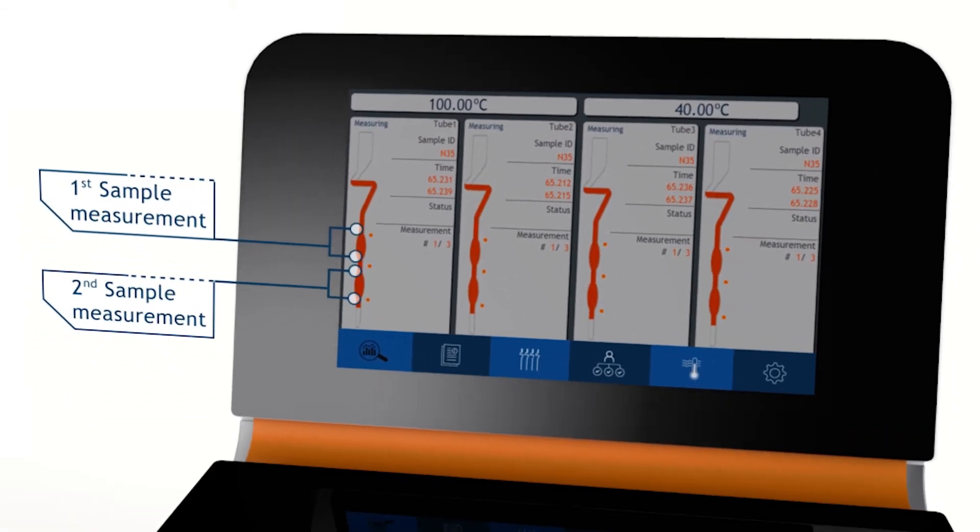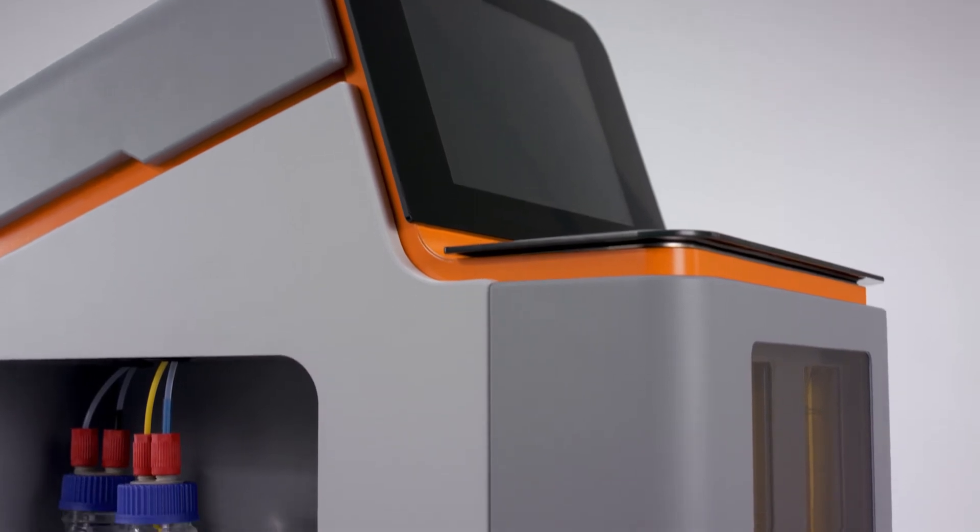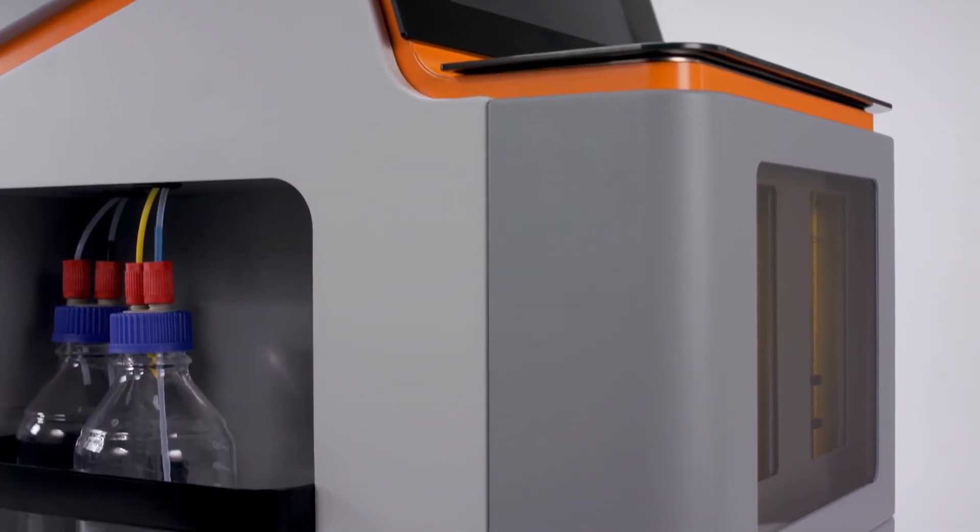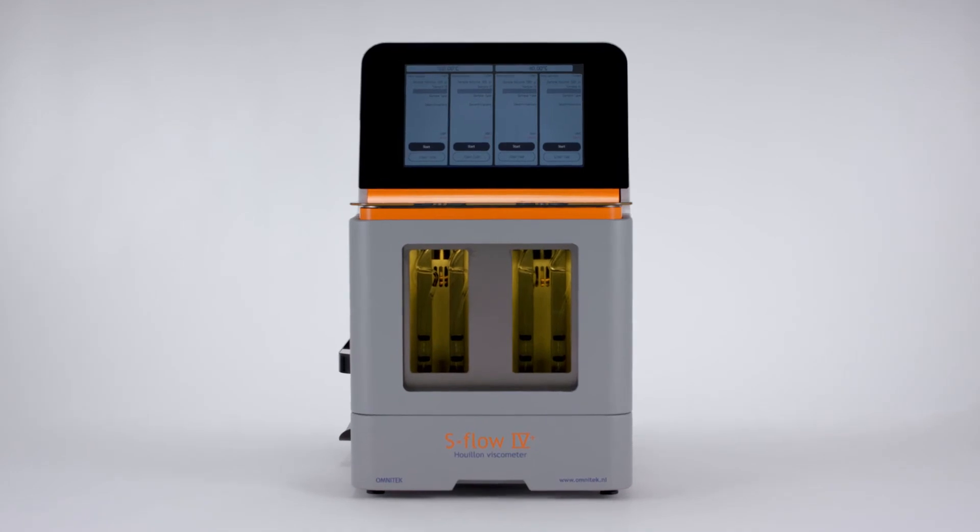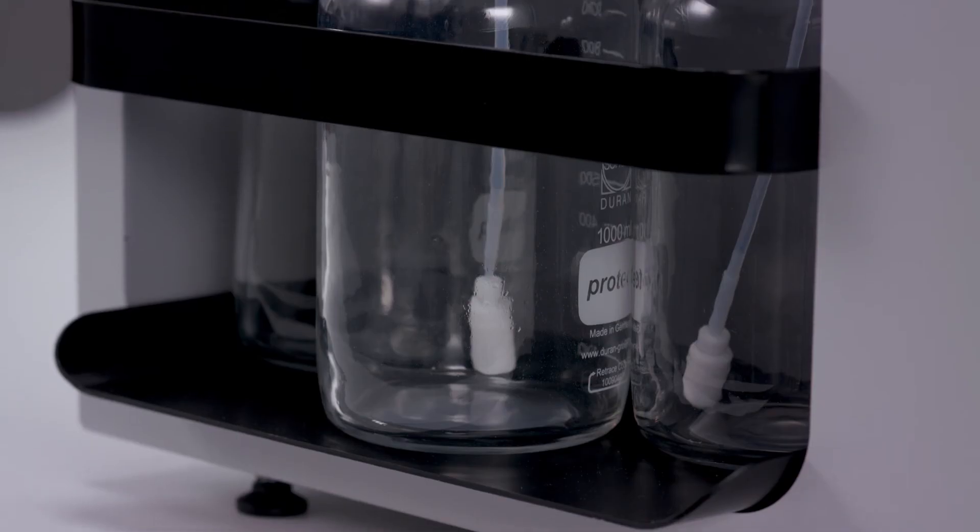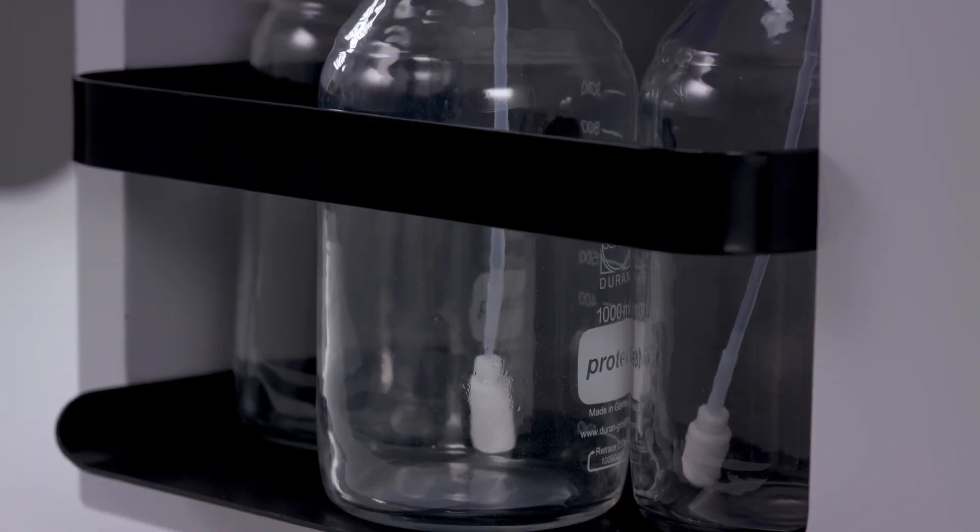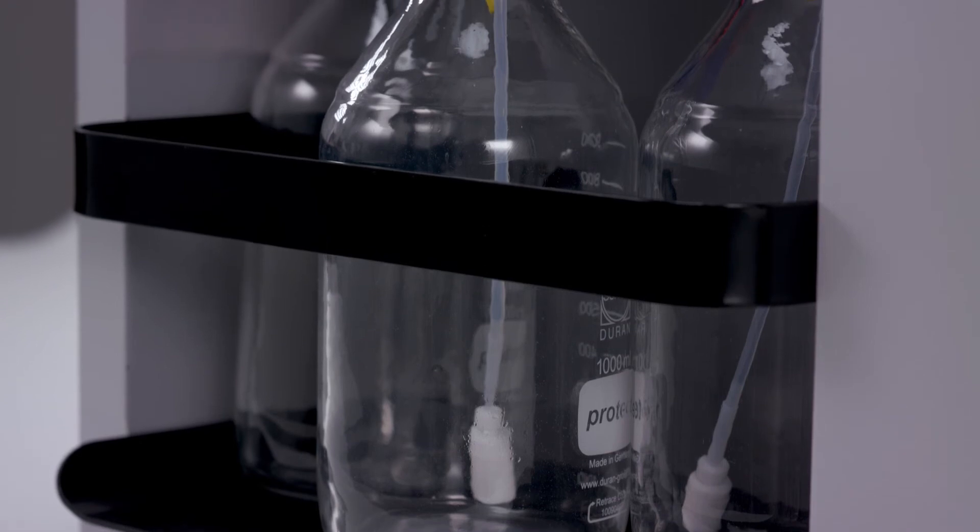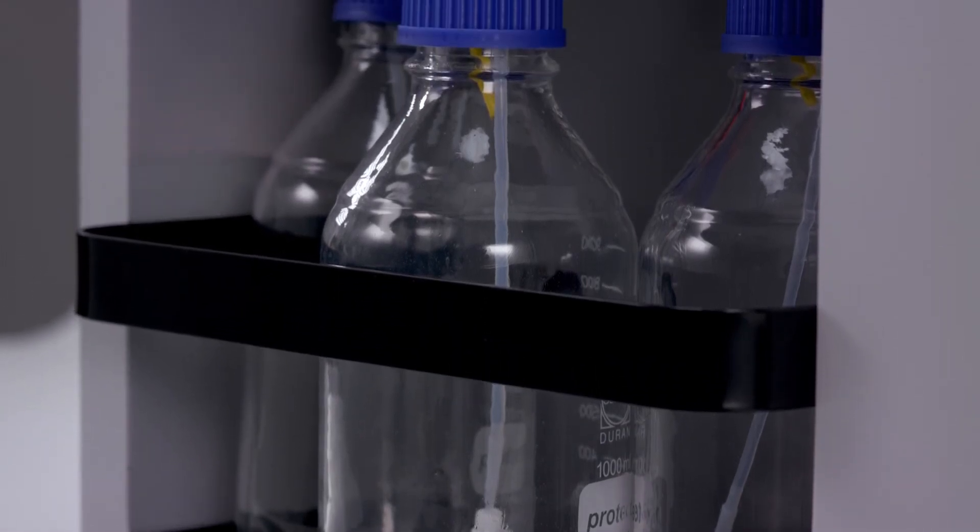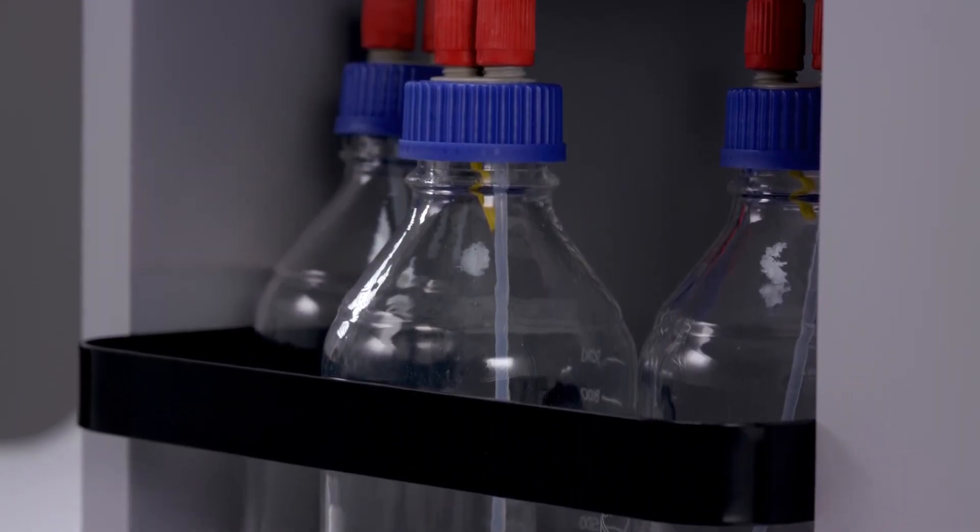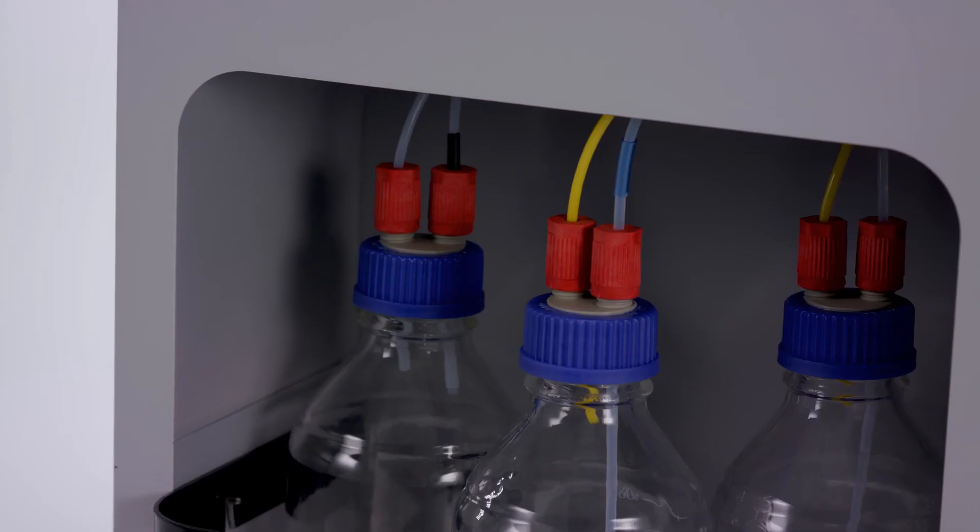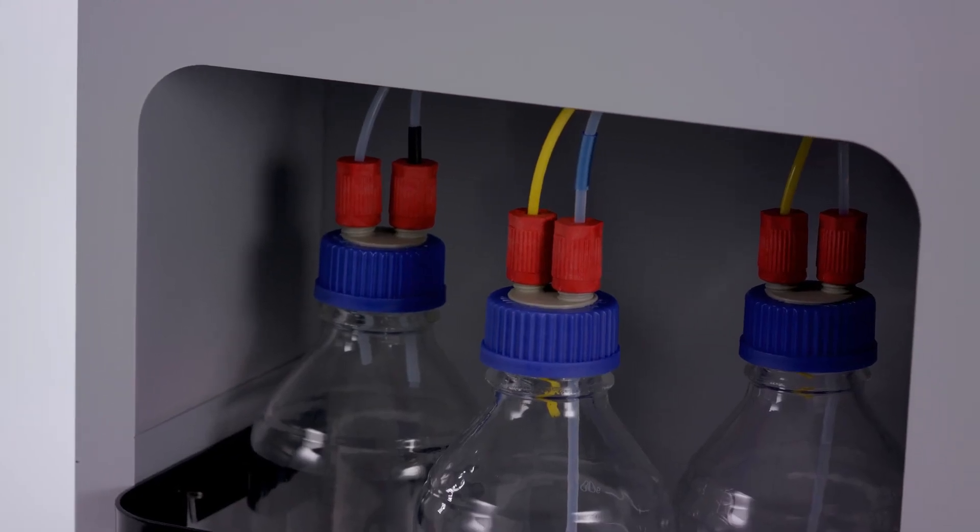The standard configuration utilizes single solvent cleaning, but for demanding applications, a dual solvent cleaning system can be fitted from factory or, if necessary, provided as an in-field upgrade. The instrument requires only a minimum of solvent, consumables and maintenance, making its operational costs extremely low.